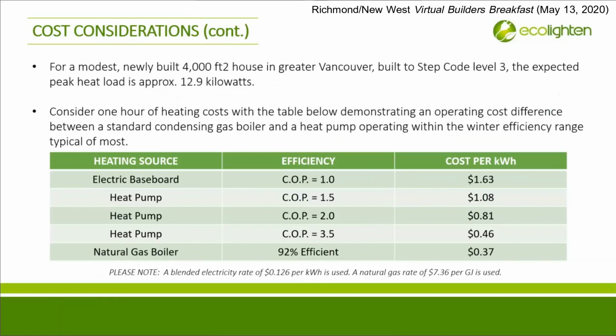So that might change. Here's the cost of heating for 1 hour at design conditions in the winter for a typical house, 4,000 square feet, built to an equivalent of about step 3 code in Vancouver. If you look at the top, electric baseboard is a 1-to-1 ratio of energy in versus heat out. In other words, a COP of 1. Down the list, heat pumps range in efficiency, and so these numbers apply to any kind of heat pump. Geothermal tends to be at the top of the efficiency scale at about a 3.5 COP or better. Air-to-water heat pumps range between a COP of 1.59 to 2.75. Air heat pumps have a similar range with some exceptions that get very close to geothermal in their efficiencies. As this chart shows, a natural gas boiler is the least expensive to operate. Again, I gotta say that this could change.